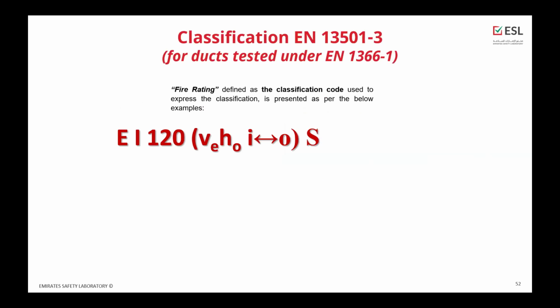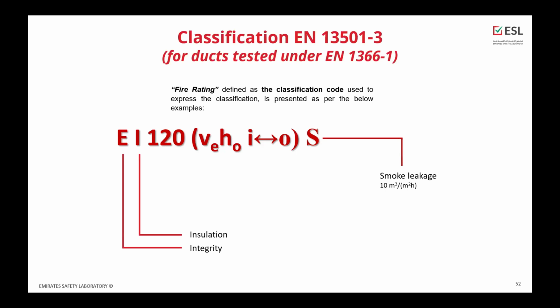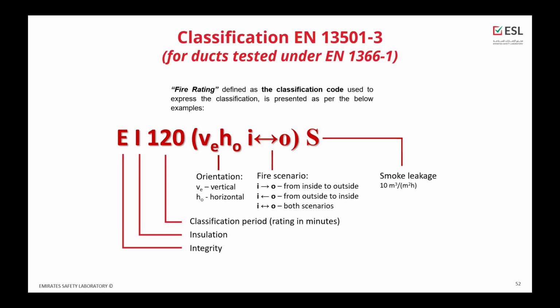In terms of EN ducts, they are classified as per 13501-3 for the ventilation duct, and the rating is defined as a classification code, as you can see here, where E stands for integrity, I for insulation, and S for the smoke leakage. The numbers are the classification period, which is the rating in minutes. VEHO is defined as the orientation, vertical or horizontal, and the last aspect is defined as the fire scenario.